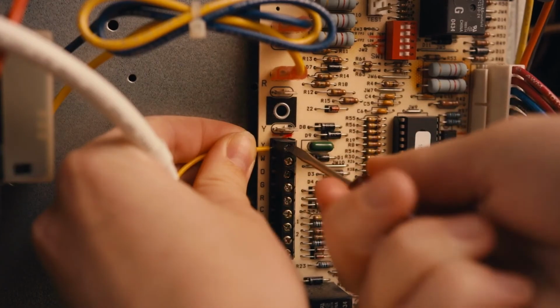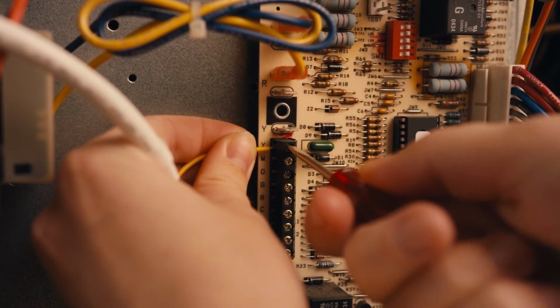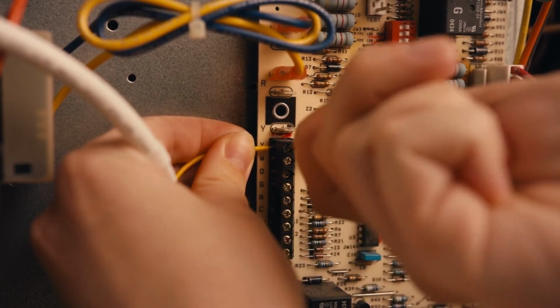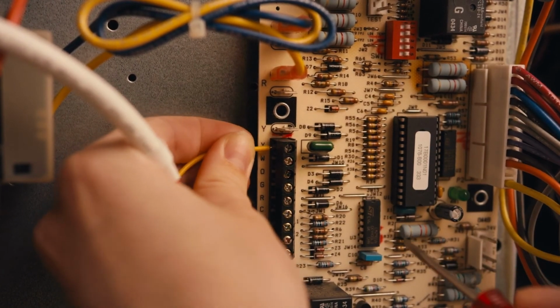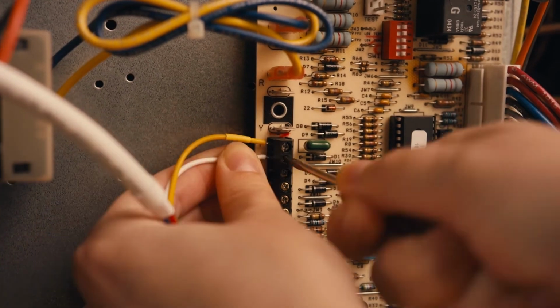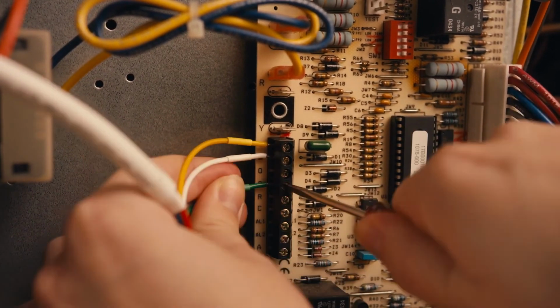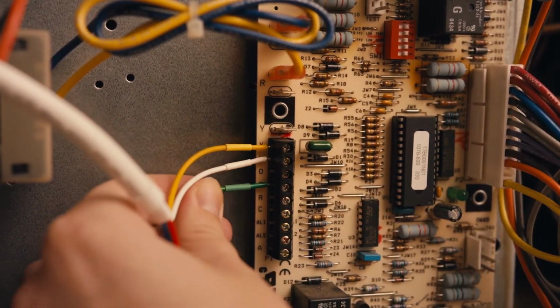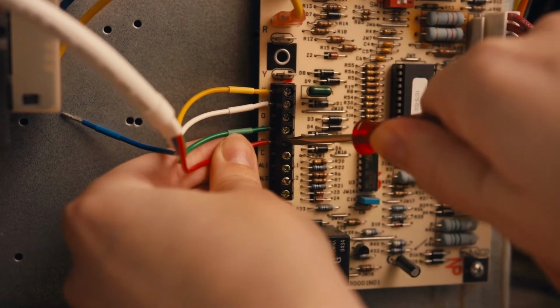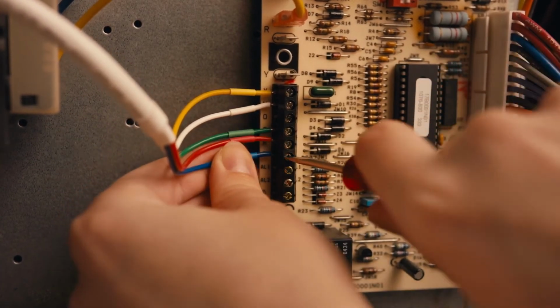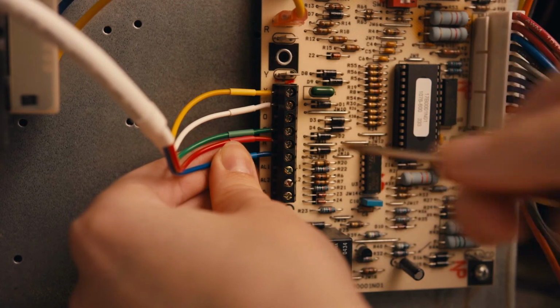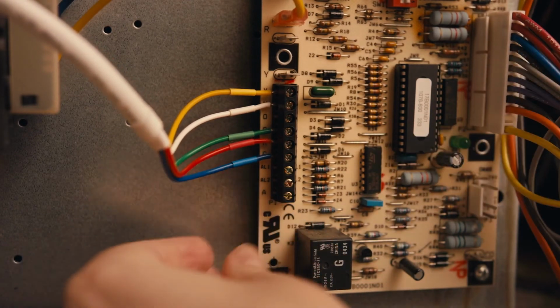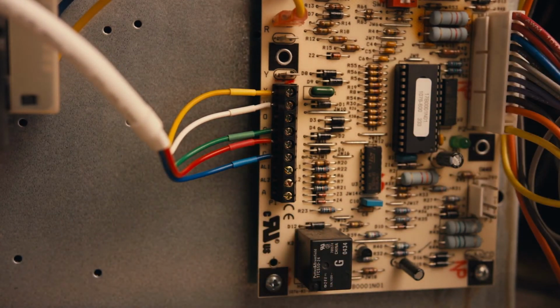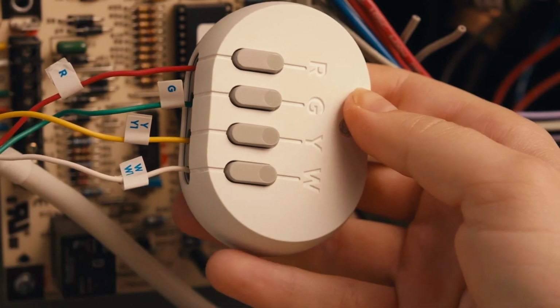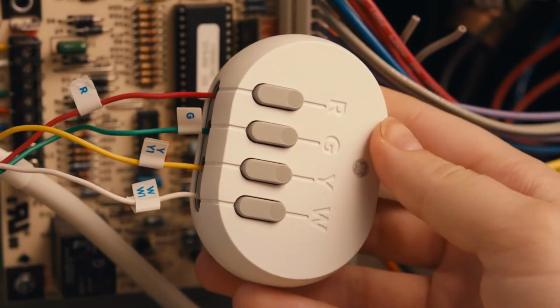Step 6. Connect the wires from the power extender kit to the appropriate terminals on the HVAC control board. The Y wire should go to terminal Y, W should go to W, the G wire should go into terminal G. The R wire from the kit should go into terminal R. C should go to C. Once you have connected the wires, lightly tug on them to ensure they're securely connected. Confirm the kit is wired between the HVAC control board and the thermostat.